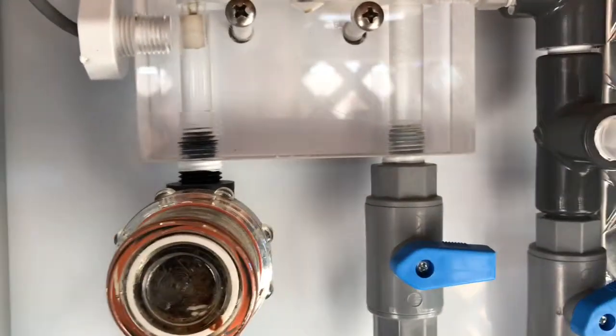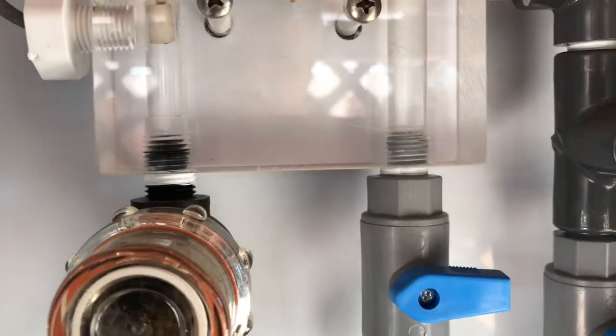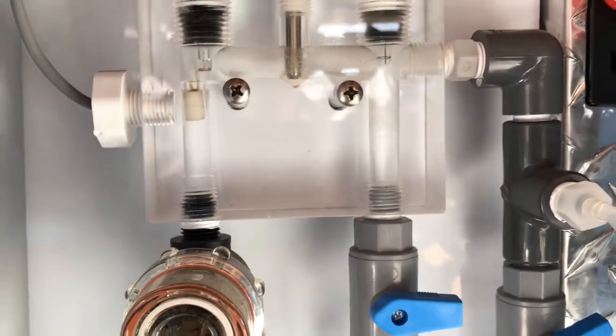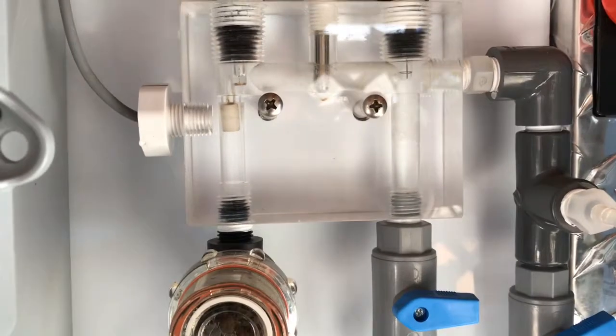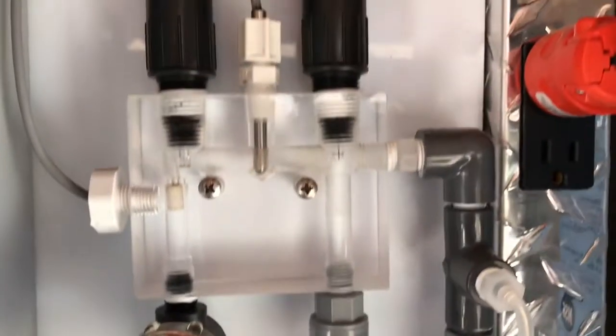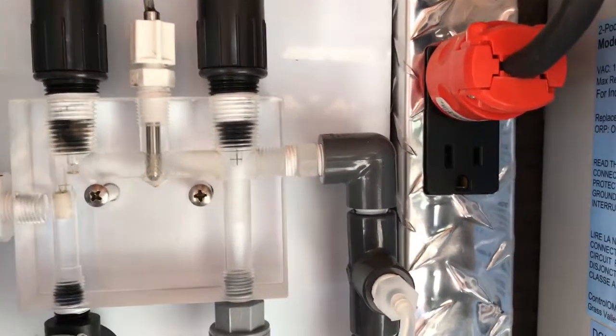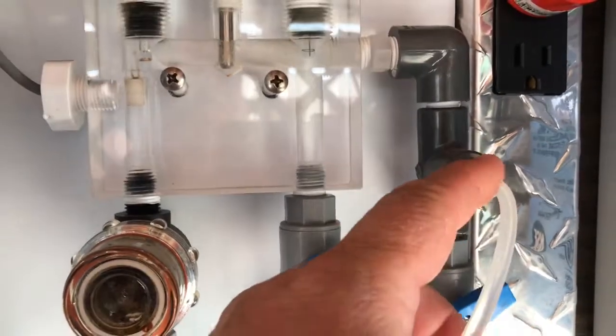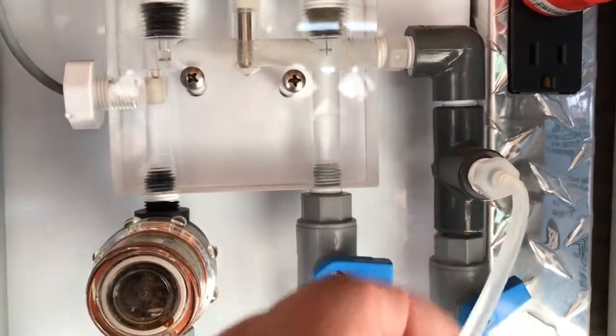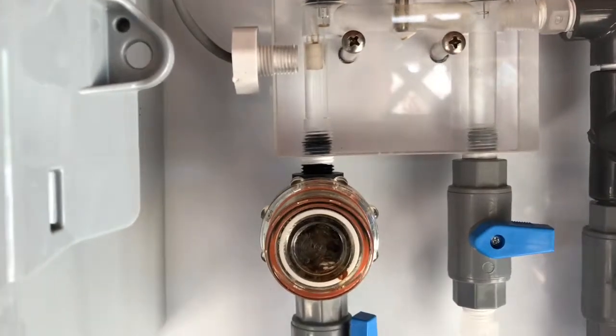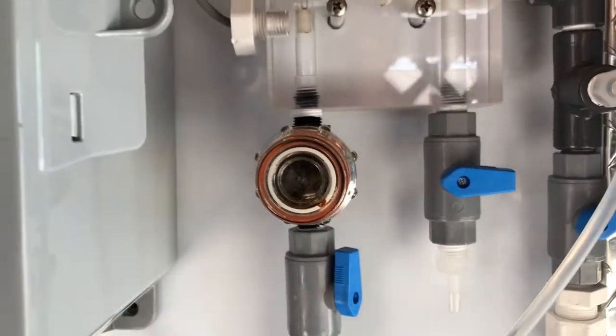The reason for that is that we don't need a lot of water flowing through here and the faster the water flows the shorter the lifespan is on the probe itself. Plus if you're using a True DPD it's good to create a little back pressure here so that we know that water is being forced to the little peristaltic pumps in the True DPD box.